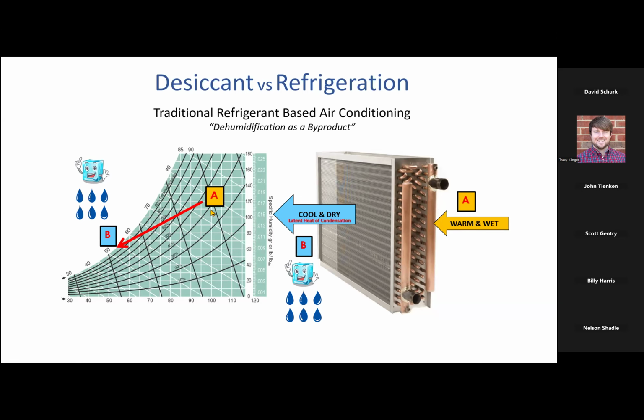Let's look at it on the psych chart. Point A might be air coming in at, let's say down here, dry bulb temperature wise around 100 degrees Fahrenheit, something like that. Who knows, right? And on the right-hand side of the chart, we see grains per pound or the amount of moisture in the air. And it might be at, let's say, 130 grains per pound. Now, my guess would be, your dehumidification design day conditions, grains per pound are probably 140 or more. So this is a little light with regards to what you might see down in your neck of the woods. But the point will be valid regardless of what we talk about.